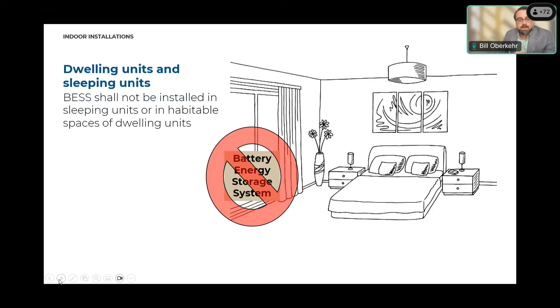There are only 3 more. A smoke alarm shall be installed in the area where the energy storage system is installed. Where a smoke alarm cannot be installed, a heat alarm may suffice. Finally, in R330.9, there's an exhaust fan requirement. These exhaust fans will automatically turn on when gases reach 25% of the lower flammable limit in the room. These ventilation fans will also be needed when toxic gas is produced during normal charging and discharging of the energy storage, like in a lead acid battery or basically any type other than lithium ion, where that is not the case.